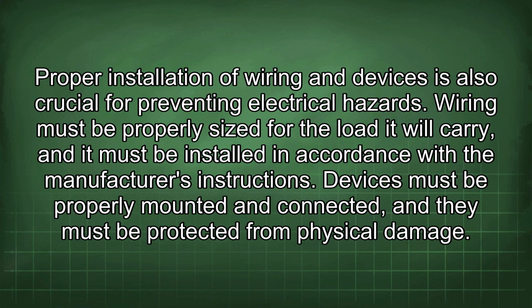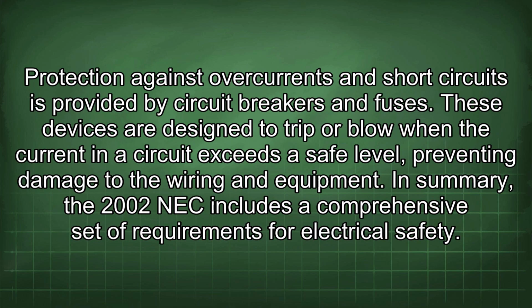Proper installation of wiring and devices is also crucial for preventing electrical hazards. Wiring must be properly sized for the load it will carry, and it must be installed in accordance with the manufacturer's instructions. Devices must be properly mounted and connected, and they must be protected from physical damage. Protection against overcurrents and short circuits is provided by circuit breakers and fuses. These devices are designed to trip or blow when the current in a circuit exceeds a safe level, preventing damage to the wiring and equipment.